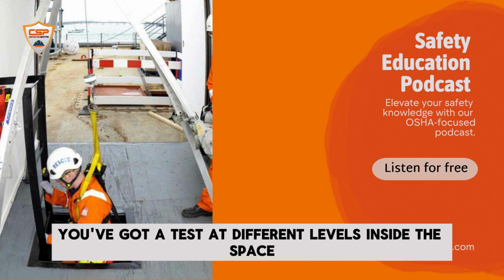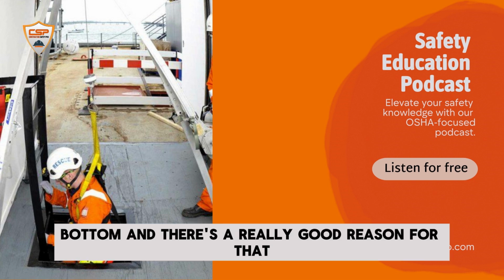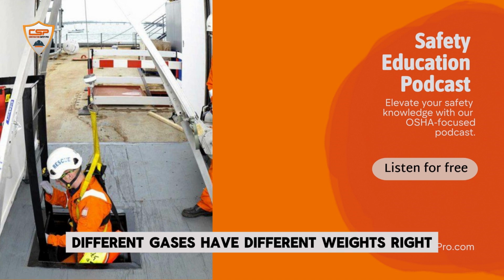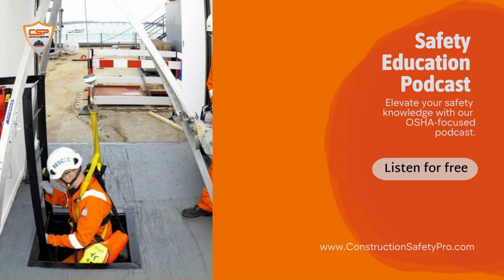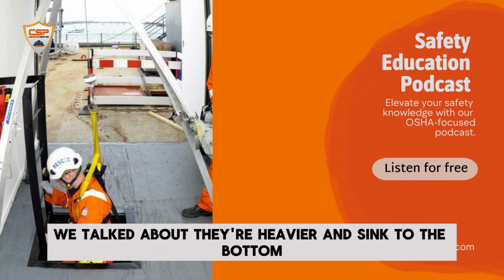Right. You've got to test at different levels inside the space, top, middle, bottom, and there's a really good reason for that. I think I know where you're going with this. Different gases have different weights, right? You got it. Some gases, like methane, are lighter than air, so they might be up near the top. But others, like that hydrogen sulfide we talked about, are heavier and sink to the bottom.